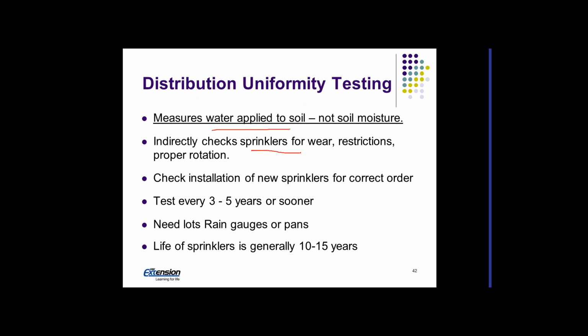Indirectly, it's going to check sprinklers for wear, restrictions, and some sprinklers have rotation, so it will check that. It also can be used as a commissioning test on a new sprinkler system to check that they were put in the correct order, because on occasion people put them in backwards, or sections of them in backwards, so that's good to know. So it can be used as a commissioning test. The recommendation is that these be done every 3 to 5 years, and that depends on the quality of the water. So if you have water that has iron in it or something, you may want to do this a little more often to check those.